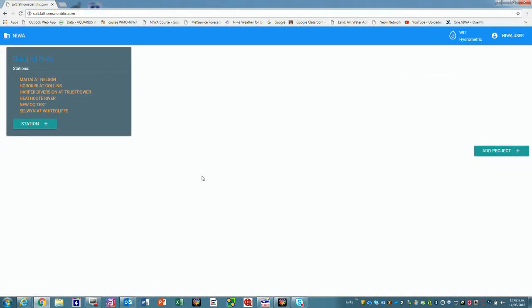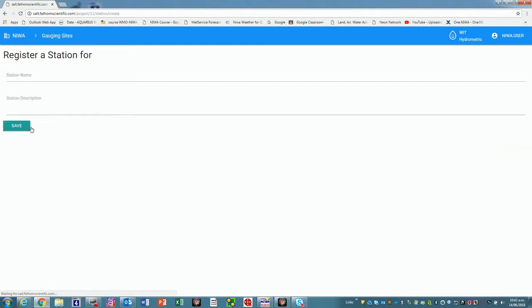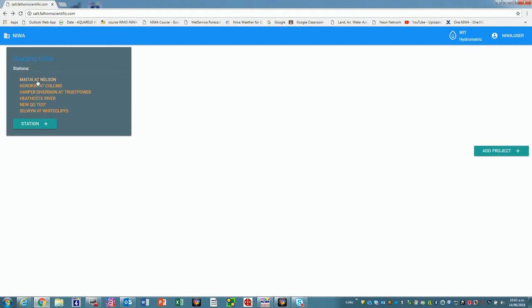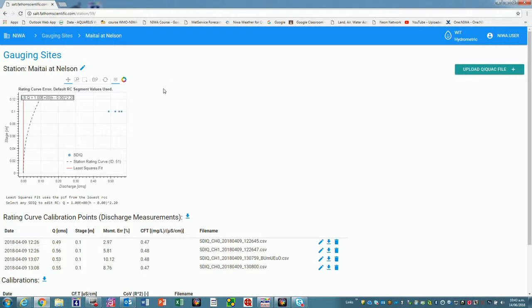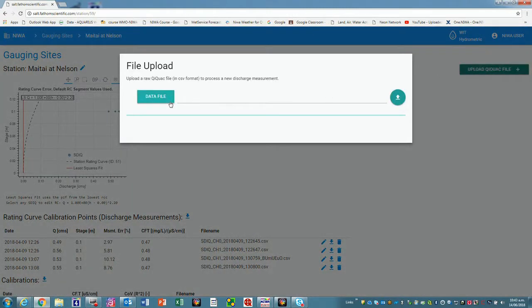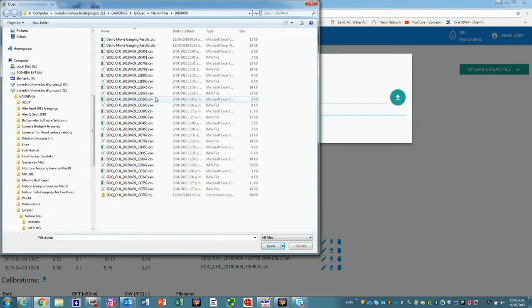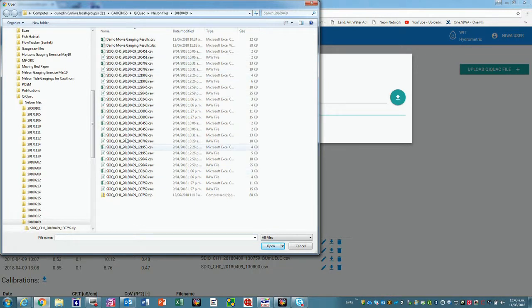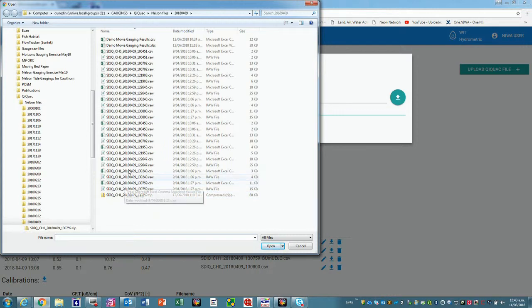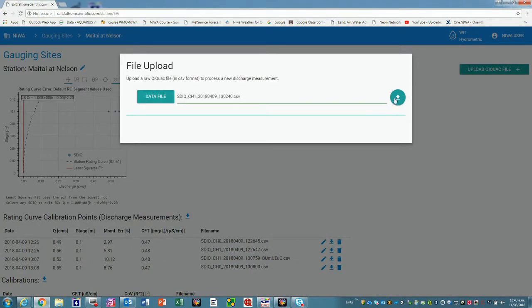There we are. So when you get into the web page, it comes up with this screen here. And it will show us the sites for New Zealand if you like, which is the way Gabe set it up. But you can add stations here for a new one as well, just a case of entering in the station name, description, saving it. And let's go back to our Maitai at Nelson example. So this is the measurements we've already loaded in here, but when you're first setting up, you want to upload a QiQuac file here. So I'm clicking on here, then go and search for the file. Which they are here. At the moment we have to load them one by one. Gabe says he is going to change this so we can upload everything concerning that. The one gauging, so there's several files here, some of them being the calibration, then the actual gauging. So you choose the file you want, and then upload it. I won't because it's already been uploaded. And then it will display below.